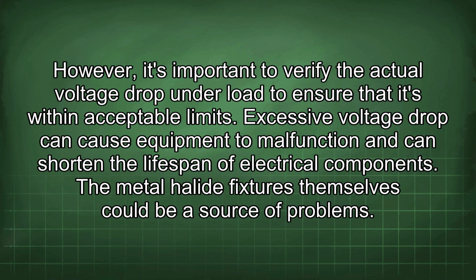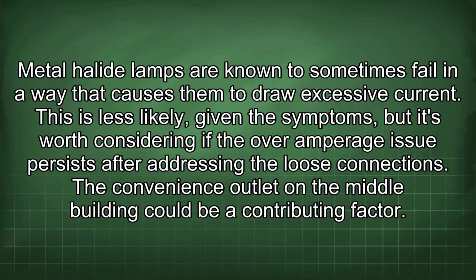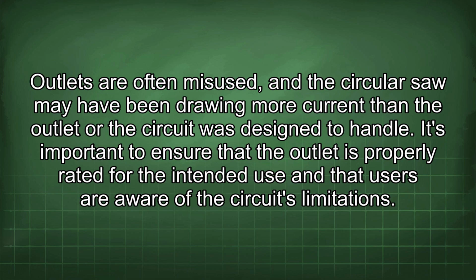The metal halide fixtures themselves could be a source of problems. Metal halide lamps are known to sometimes fail in a way that causes them to draw excessive current. This is less likely, given the symptoms, but it's worth considering if the over-amperage issue persists after addressing the loose connections. The convenience outlet in the middle building could be a contributing factor. Outlets are often misused, and the circular saw may have been drawing more current than the outlet or the circuit was designed to handle. It's important to ensure that the outlet is properly rated for the intended use and that users are aware of the circuit's limitations.